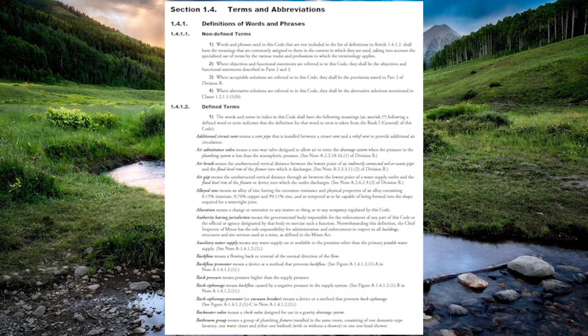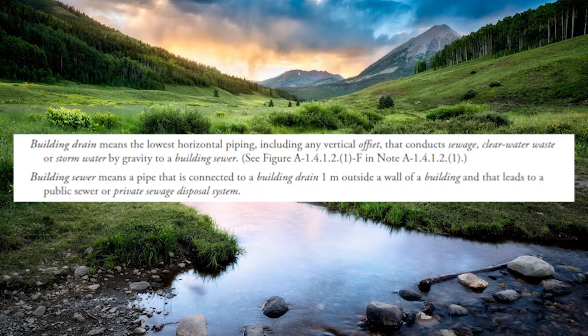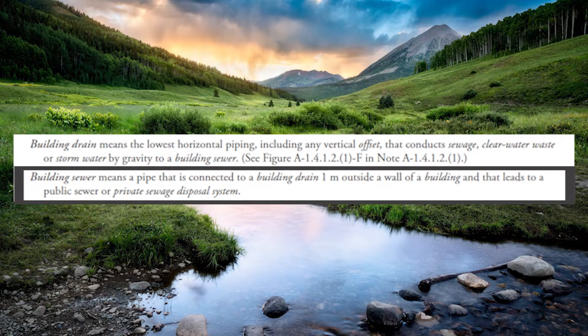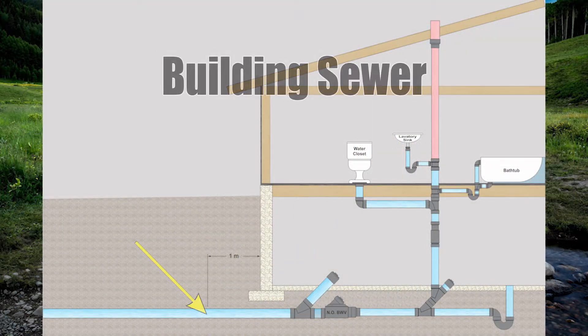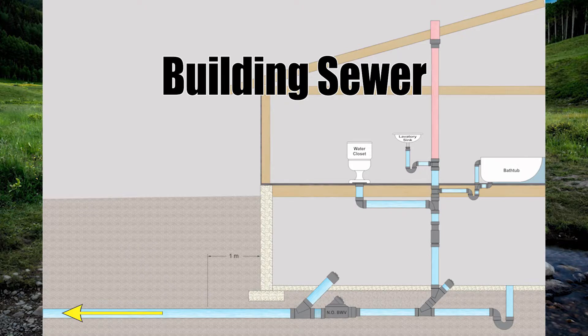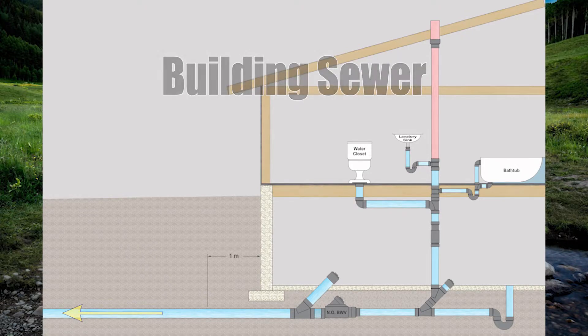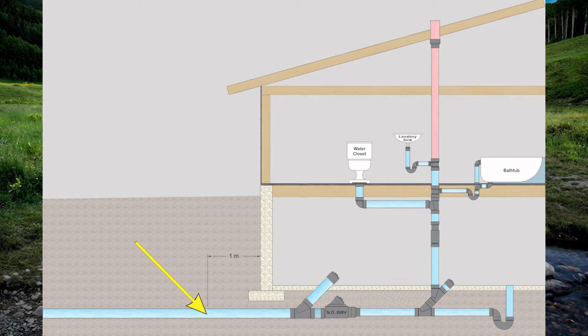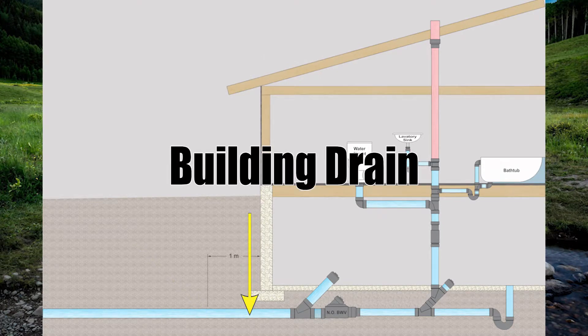The plumbing code has a number of definitions right near the beginning of the code in Section 1412, Defined Terms. Building sewer means a pipe that is connected to a building drain one meter outside a wall of a building, that leads to a public sewer or private sewage disposal system. So the building sewer begins one meter beside the building and travels all the way to either a septic tank or the city main.